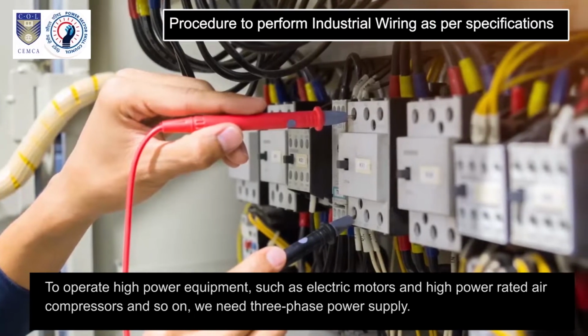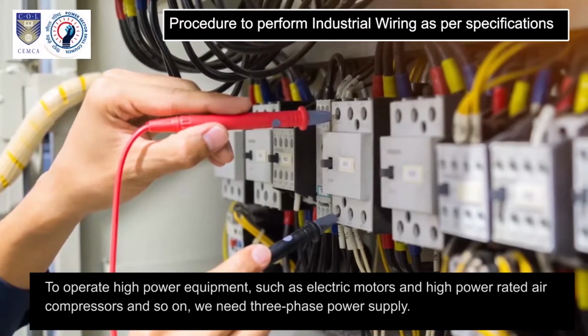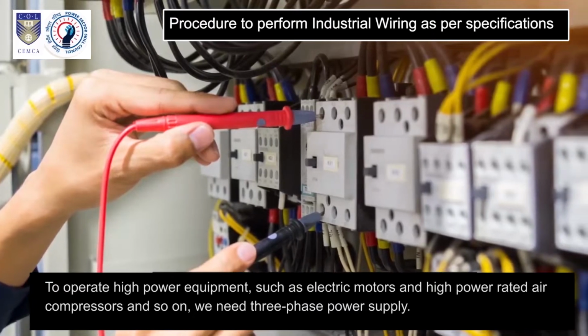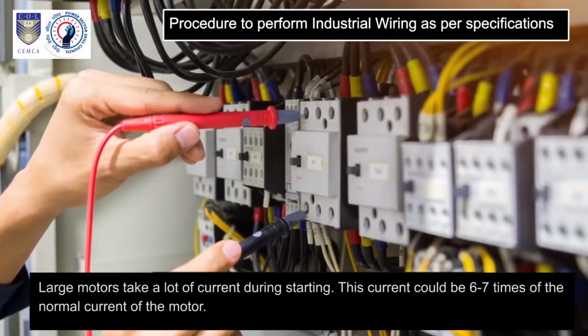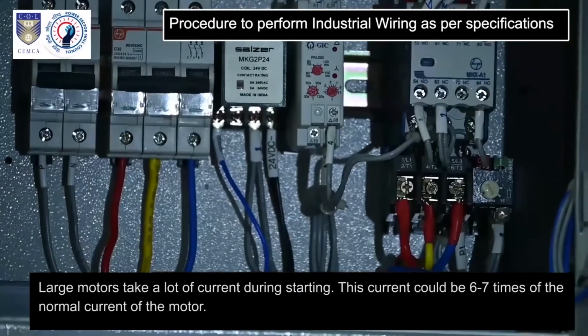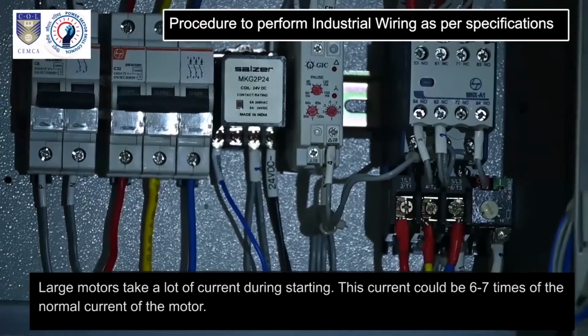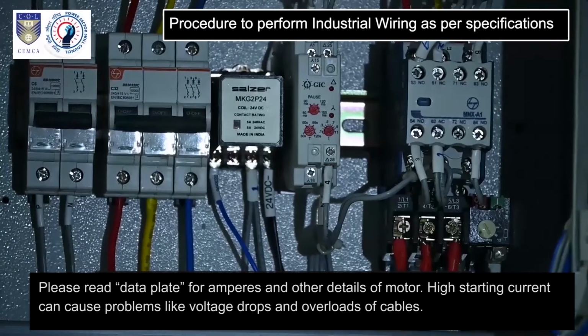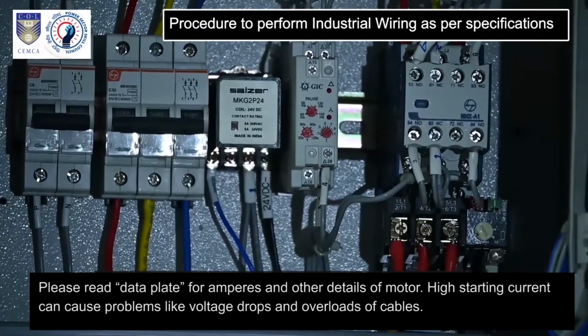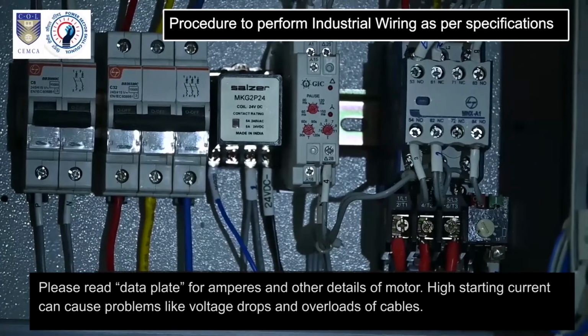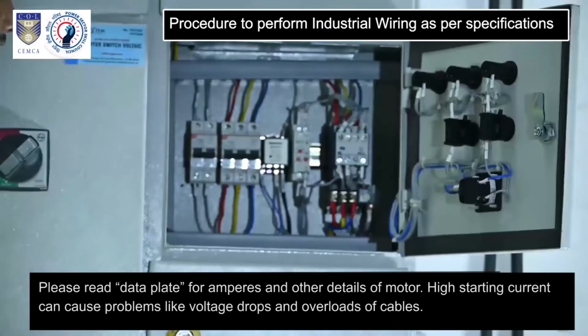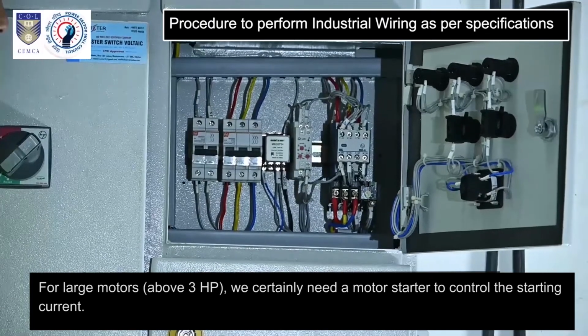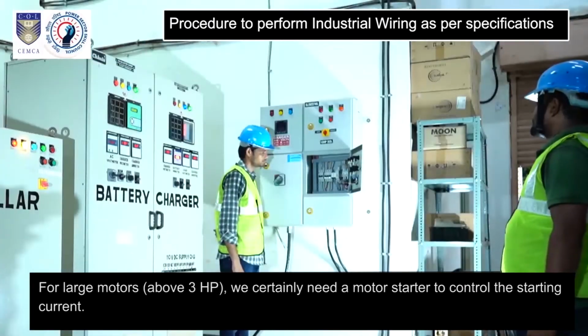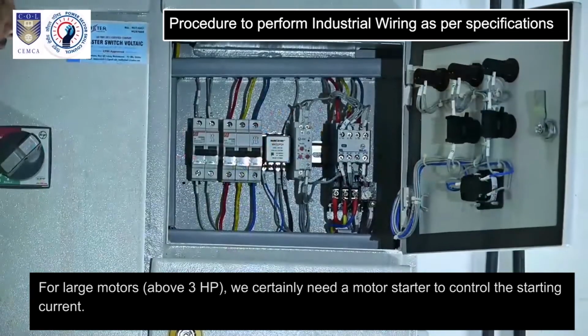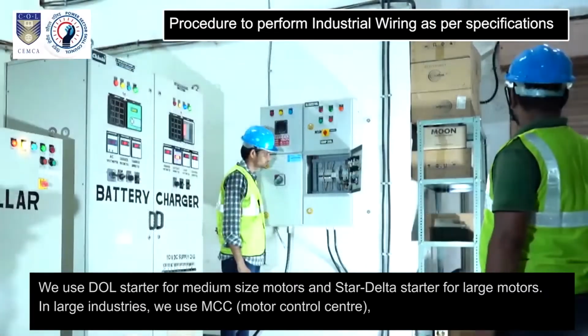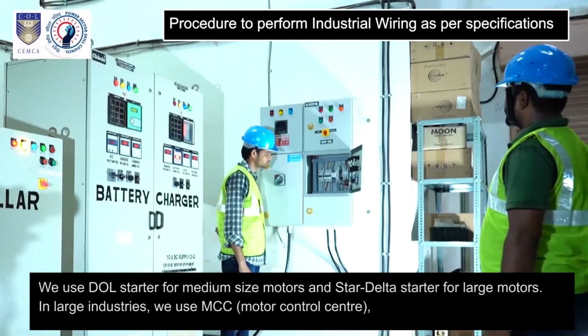To operate high-power equipment such as electric motors and high-power rated air compressors and so on, we need three-phase power supply. Large motors take a lot of current during starting. This current could be 6-7 times of the normal current of the motor. Please read data plate for amperes and other details of motor. High starting current can cause problems like voltage drops and overloads of cables. For large motors above 3 HP, we certainly need a motor starter to control the starting current. We use DOL starter for medium-sized motors and star delta starter for large motors.